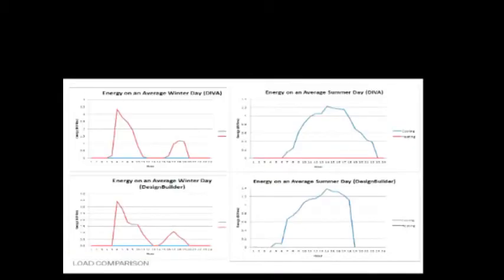And what we're looking at is a typical summer and winter day for both heating and cooling. And as you can see here, there are some discrepancies in the schedule. That's why it's dropping right off here, whereas DIVA is slowly ramping down until 11 o'clock. So those discrepancies can be attributed to this difference in the schedules.